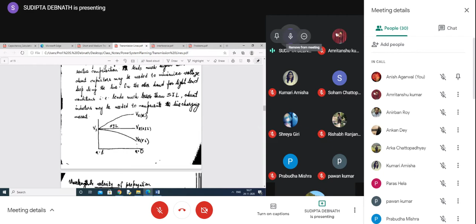And some other things about the SIL. See here why it is called SIL. The amount of MVAR produced is dependent on the transmission line's capacitive reactance. So the amount of MVAR is actually V square by XC, and the amount absorbed is through the inductor. It is I square into XL because it is the electromagnetic energy. Under surge impedance loading, this MVAR should be equal to this MVAR. So I square XL, you can also write V square by XC, as VAR.